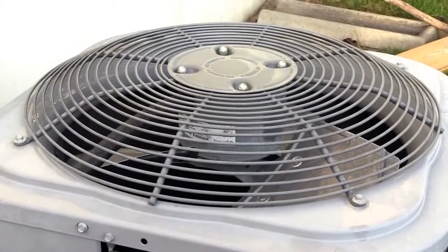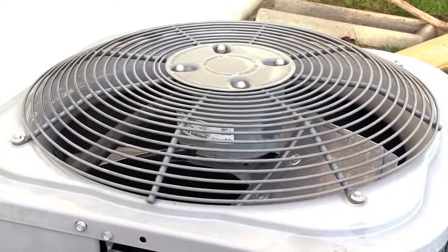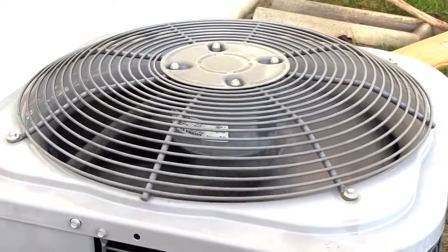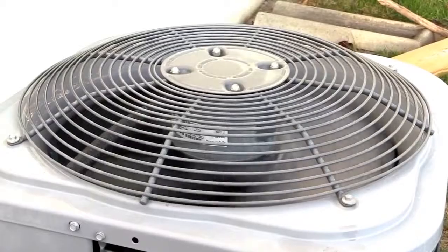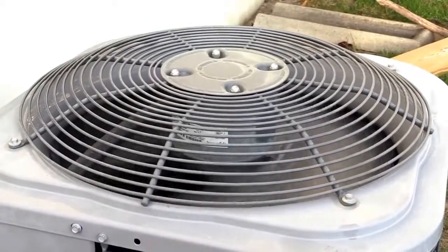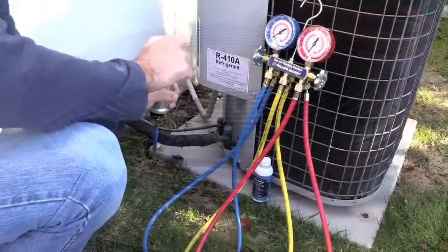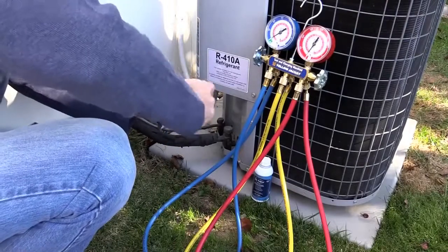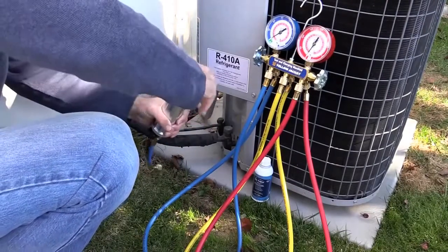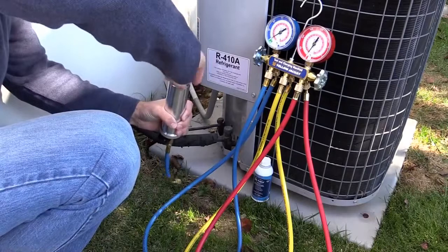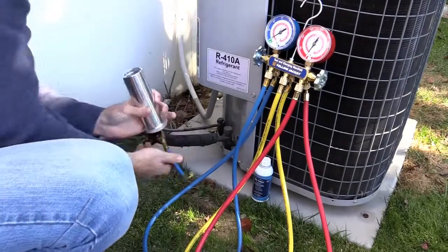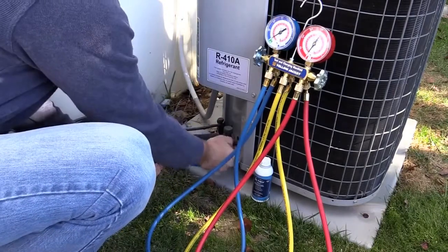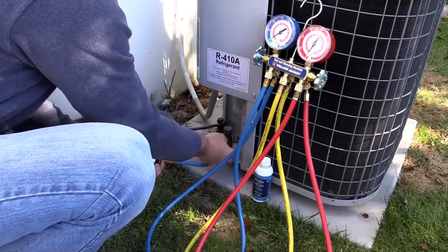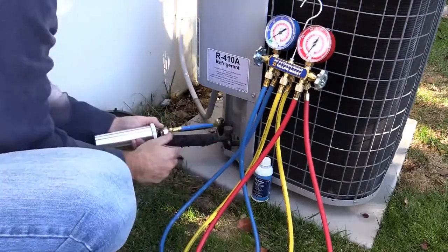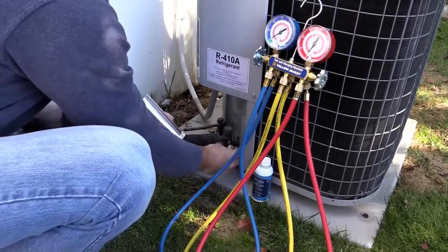First, make sure the system is running and the low side and high side service ports are properly identified. For heat pumps, make sure the system is in cooling mode. Open the AC Renew injector by turning the silver disc beneath the Schrader fitting counterclockwise. Remove the cap from the low side service port, and before connecting, check to make sure the hand valve of the AC Renew injector is in the closed position.